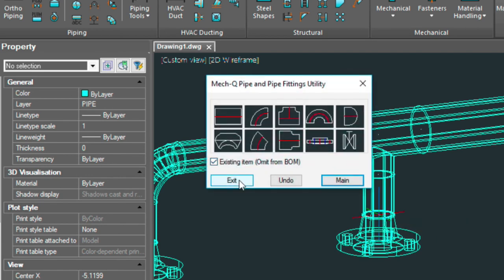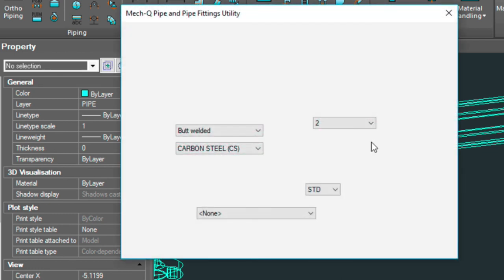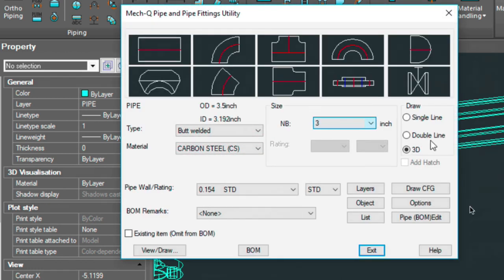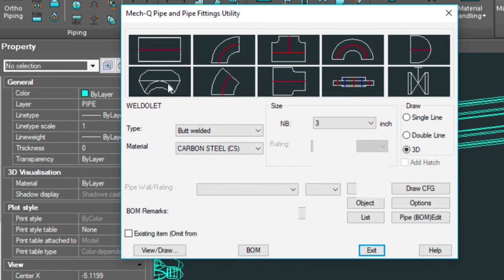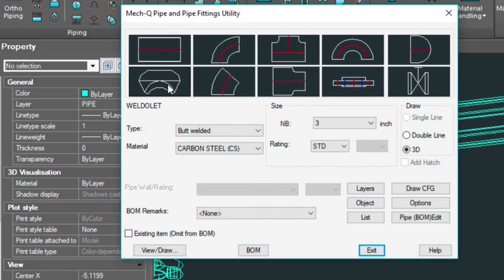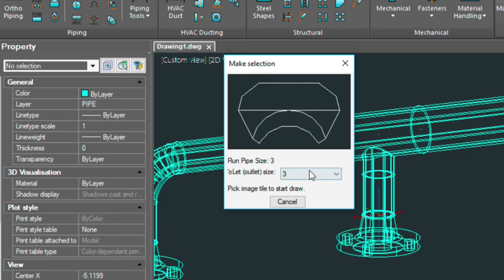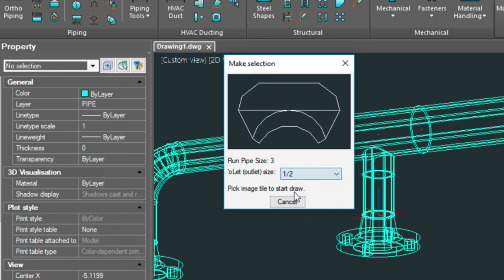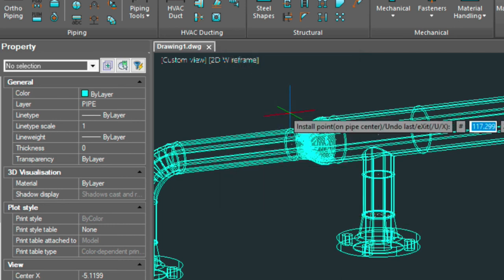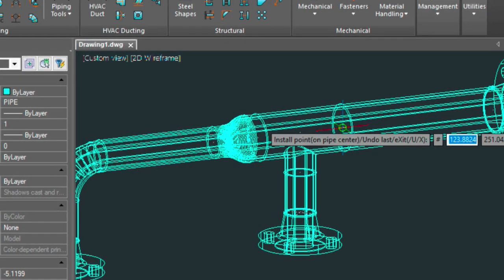And lastly let me show you how to do weld-o-let, which is right here. Let's go out to the main menu first. We need to change this to three inches. So we have this three inch selected because we want to put the weld-o-let on this side of the model where our three inch pipe is. So now we're ready to select the weld-o-let. And click the view draw button. And our outlet size is going to be half inch. We need to pull that down. And then we just select the icon here to start drawing. We're going to select the center of this point here. That's the end of our tee. We'll left click there once we see the circle there, once we know we're snapped into the center of that pipe.